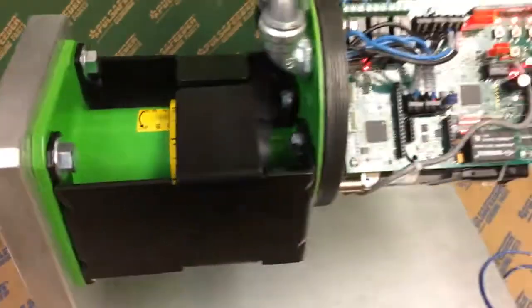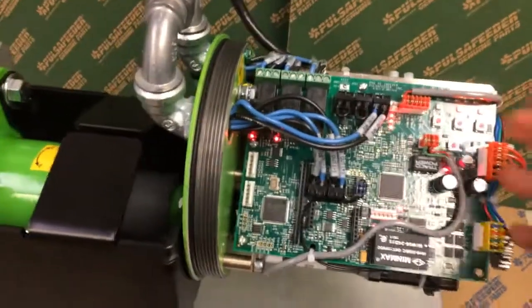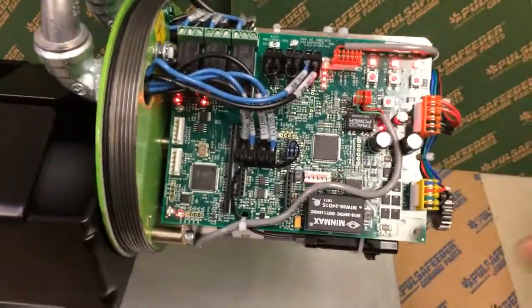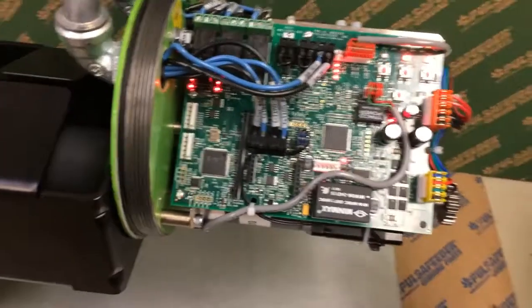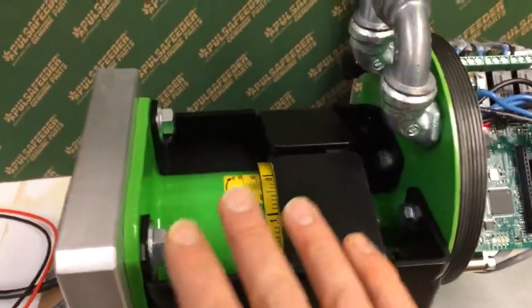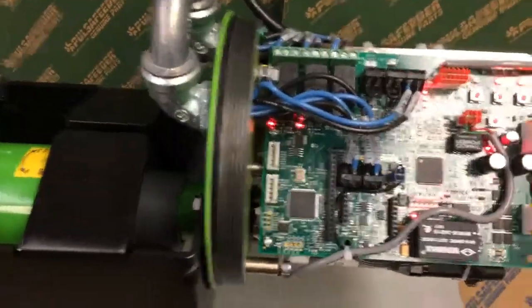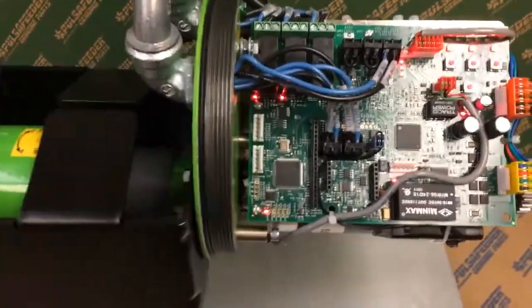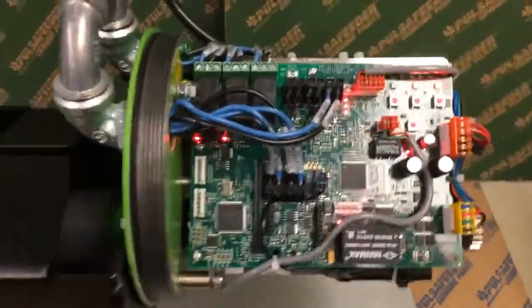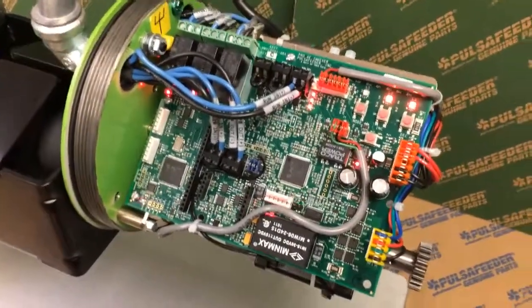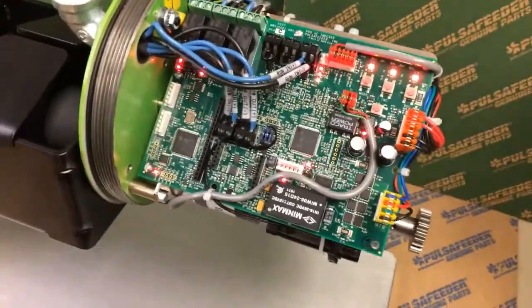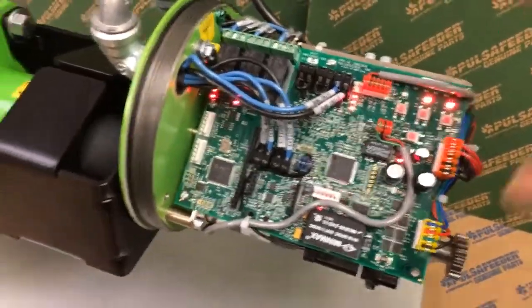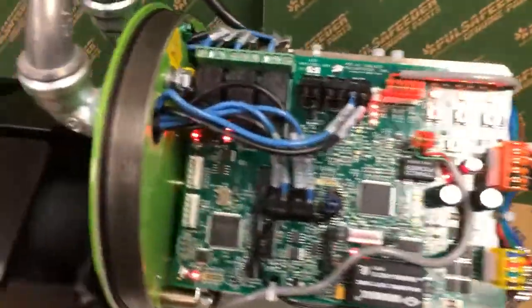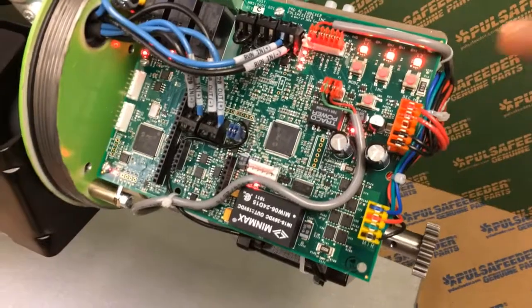At this point, if the actuator wasn't attached to the pump, if they were completely decoupled, I'd turn the power off to the actuator because I'd know that it's at 50%. And I'd set the pump at 50% in accordance with the scale, and then I'd bolt the two together. So now the actuator thinks it's at 50% and the pump is at 50%, and they're pretty close, but they're not really calibrated yet. That's a process we're going to use next. Once they're coupled together, and the actuator is at what it thinks 50% is, and the pump is at what it thinks 50% is, now I'm going to proceed with mechanical calibration.